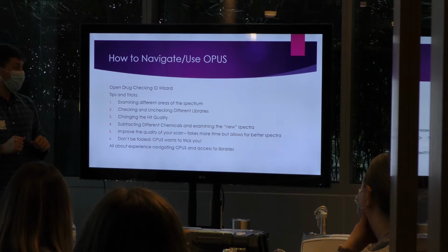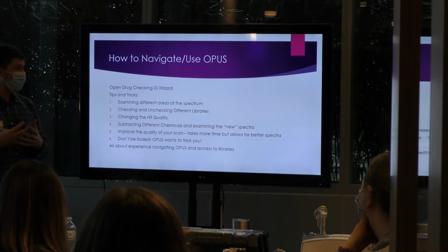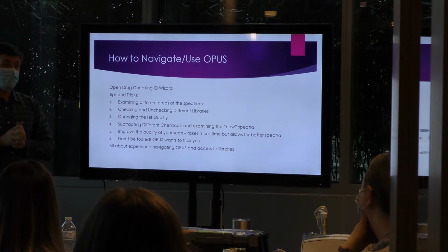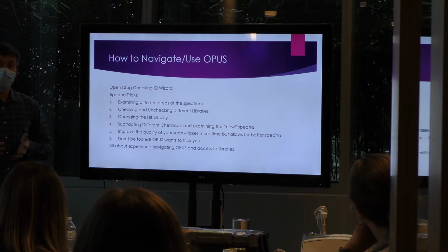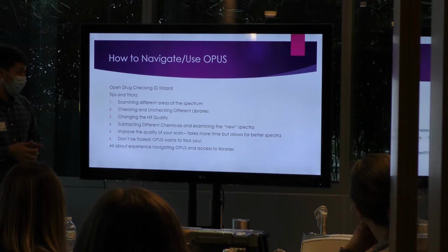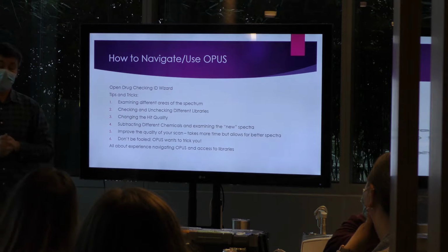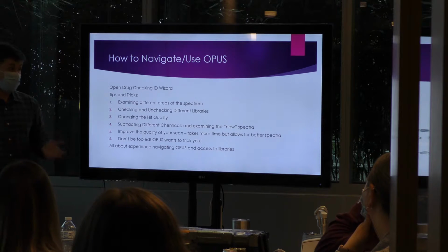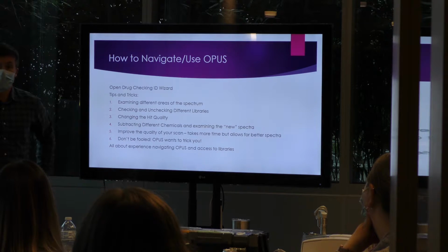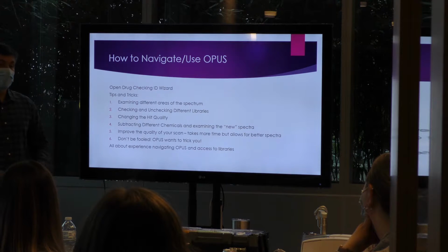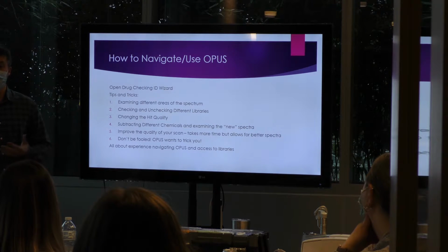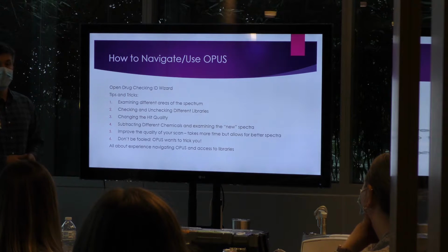So Bruker, I don't know if this comes standard, but they give you 4 pharma libraries. If you have anything that looks like a pharmaceutical drug that looks legit, you should check those pharma libraries, because they will most likely be very accurate if it is a true pill. You will just come up with, oh, 988 hit quality. It's a perfect match to what you'd see in a pharmaceutical grade pill of this sort.